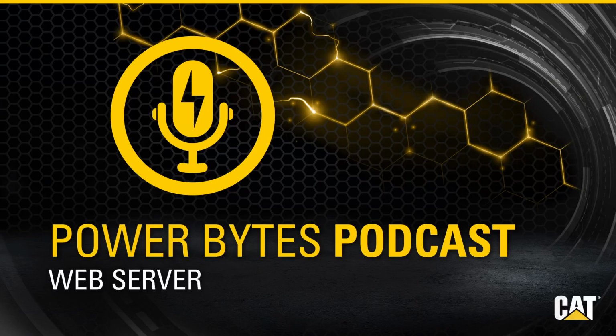So it's really located, as the name implies, embedded into our controller. But don't worry, connecting is very easy. All you need is simply a PC and an Ethernet cable to get going. We'll have an RJ45 jack near the controller to make plugging in easy, and then the other end, of course, just to your PC. After just a few minor configuration steps from there, you need the IP address of the controller, and that can be easily located from the front face of the HMI, or human machine interface, in the TCP/IP SCADA data link menu on our screen.